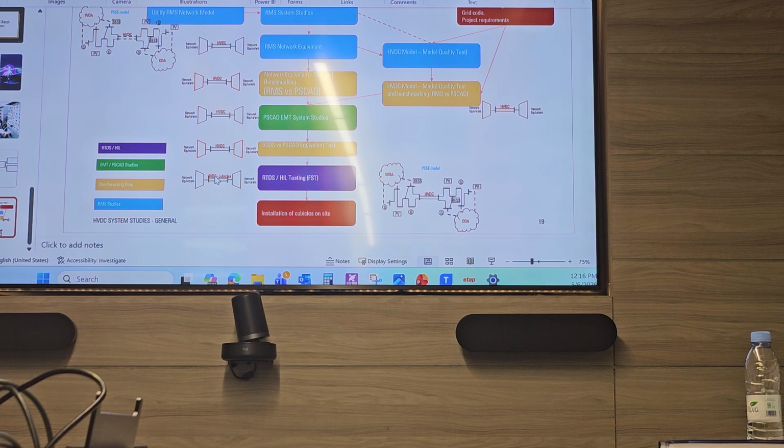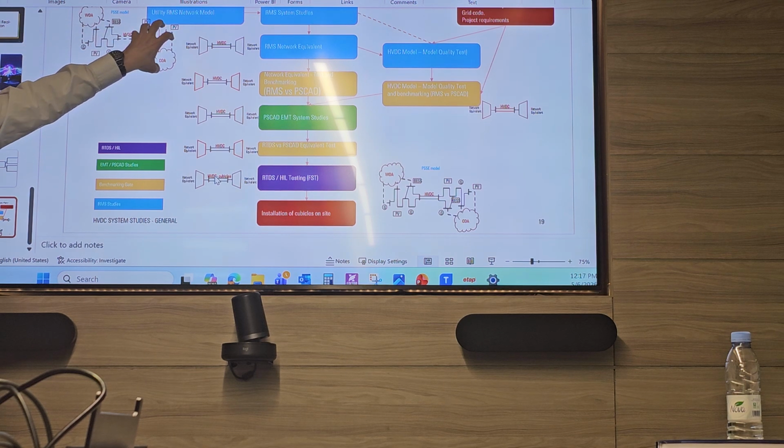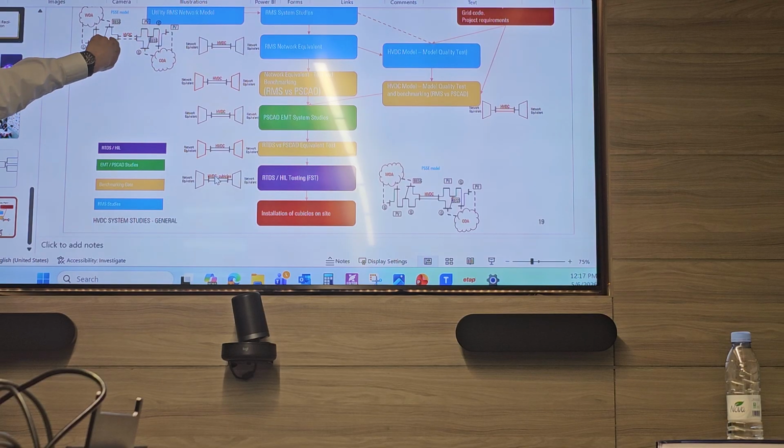So, what we mean by grid forming is that it can stand on its own. So it can start from zero. No need for any interaction with the system. But in grid following, what do we mean? With grid following, you need to have something behind. You see, I explained here. If you want to make grid forming for gas, like out here, you need to have energy from some place to push it through here and to provide power to loads here.